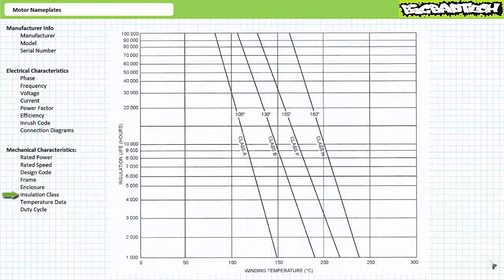Insulation class. The class or insulation class entry on the motor nameplate refers to the lifespan of the insulating material given standard operating temperatures. All else being equal, the higher the insulation class letter, the longer it's going to last at higher temperatures. A motor with Class A insulation will last 20,000 hours at 105 degrees Celsius, whereas a motor designed with higher quality Class H insulation is designed to last the same 20,000 hours at 180 degrees Celsius.